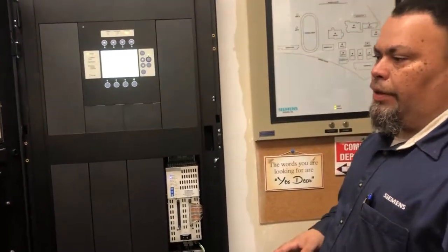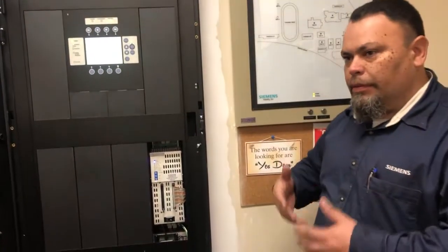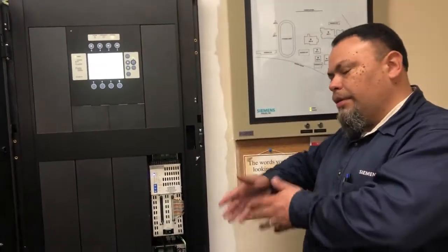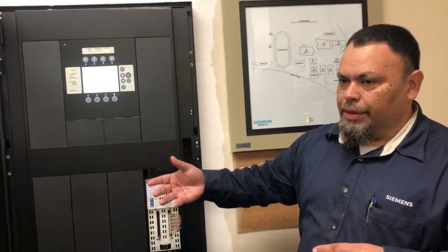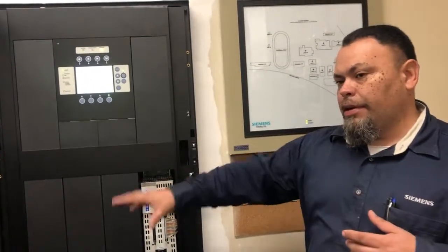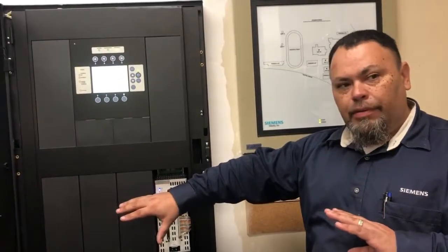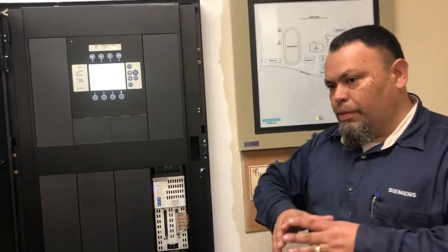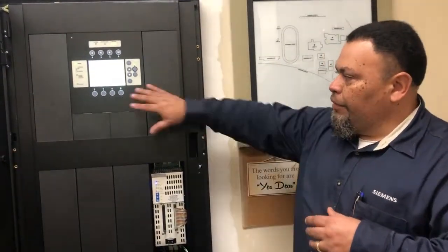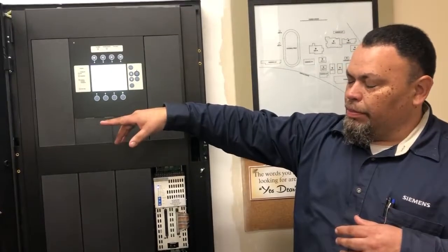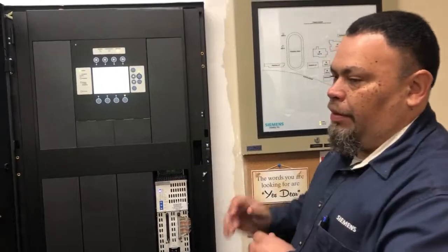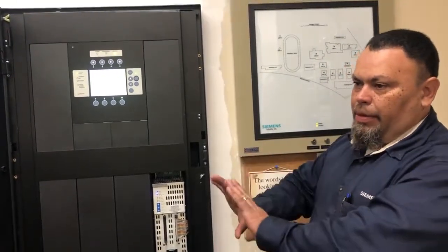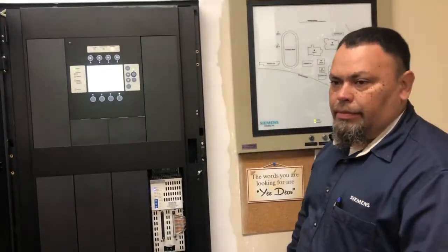Again, this is a district issue. Each district does things differently. Some districts will allow the custodians to reset the pull stations. Other districts want district personnel to come to the site and reset it for you. Whatever your district's protocol is, before you reset the system, the pull station will need to be reset. By doing that, you have to open it up and reset it internally, put it back together, and then you can reset the system.